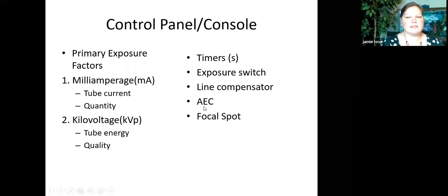There's this thing called AEC. Our tube does not have AEC, but there is on the digital room. I'll show you the AEC stuff. We don't have AEC. That's considered automatic exposure control. We will talk about that in probably week 3 or 4 of this class. And there's a setting for what we call the focal spot. And that's other things on the control panel. So all of these little buttons and things we're going to look at individually, and you guys are going to know them inside and out just today. Know what's on the control panel, mostly these two over here, the primary things we set, milliamps and kilovoltage.